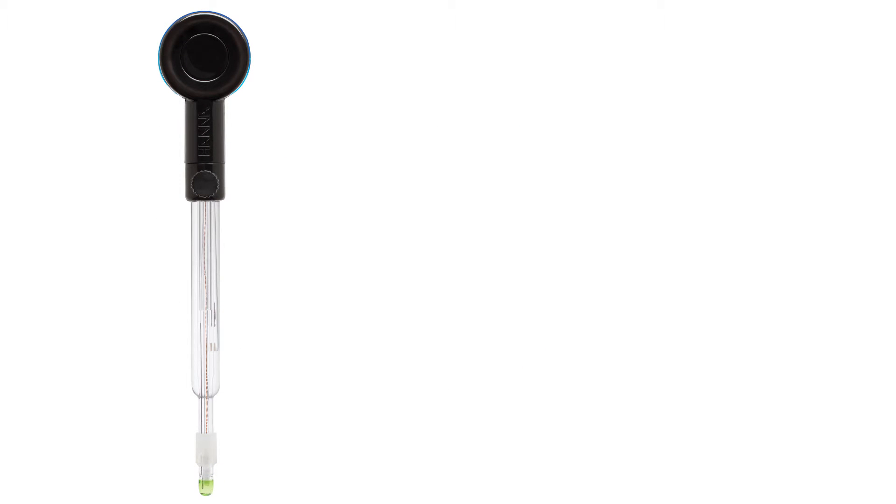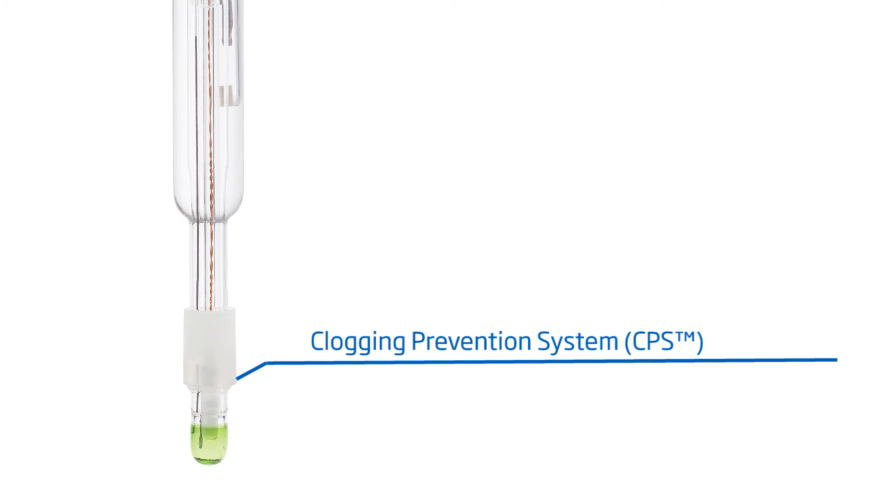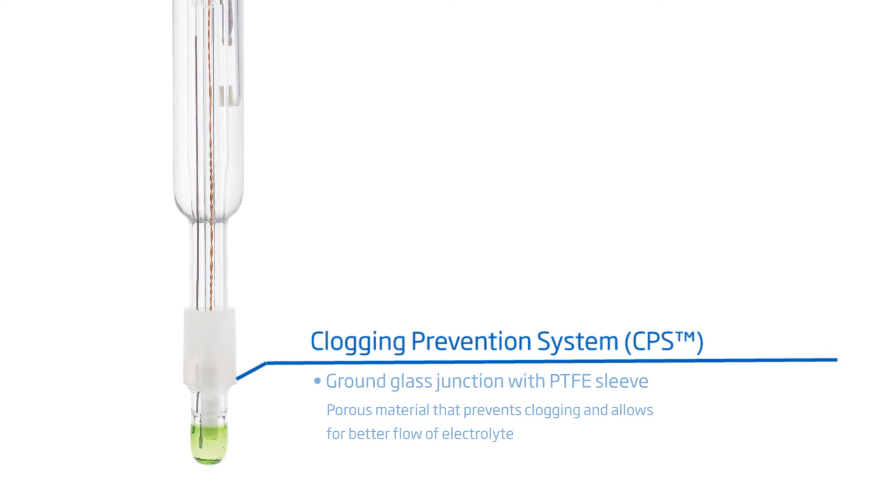One of the most unique features of this pH electrode is the HANNA clogging prevention system. The electrode has a ground glass junction coupled with a PTFE sleeve to prevent particulates within the sample from clogging the junction.